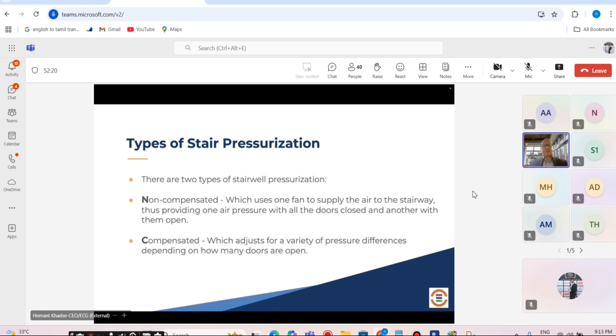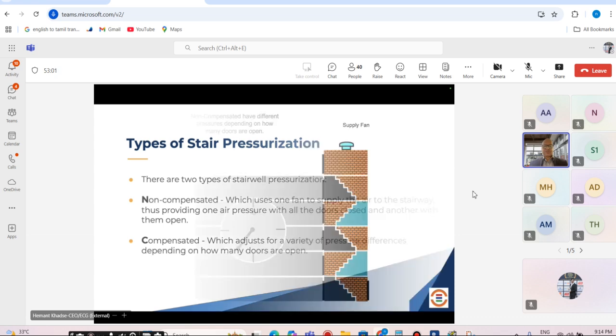At times, maybe the staircase is only pressurized, but the lobby is not. The lobby has got a lot of windows which are in the form of louvers. You expect some of the openings which will induce the fresh air to come in through the openings which are available. The systems will have different calculations, and code has given how these systems can be defined, and your staircase pressurization fans can be engineered.